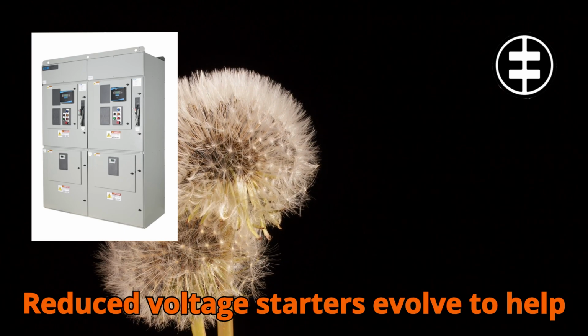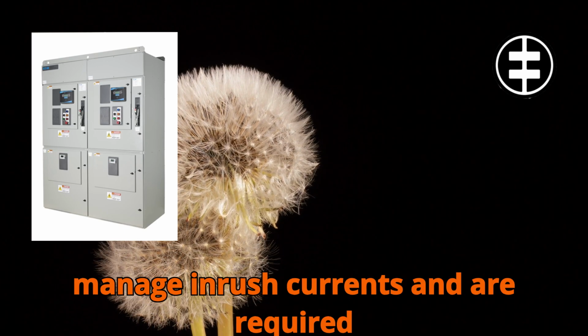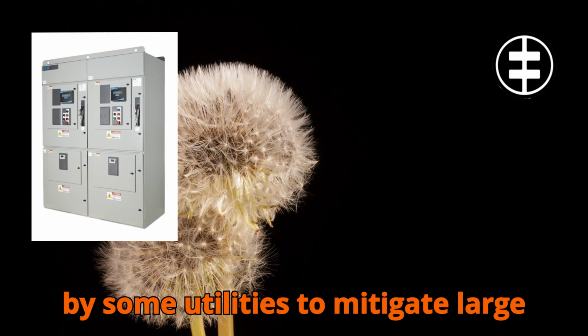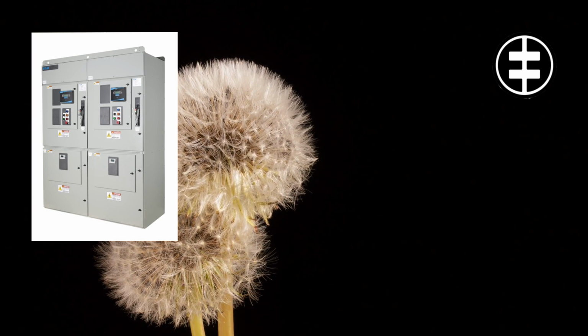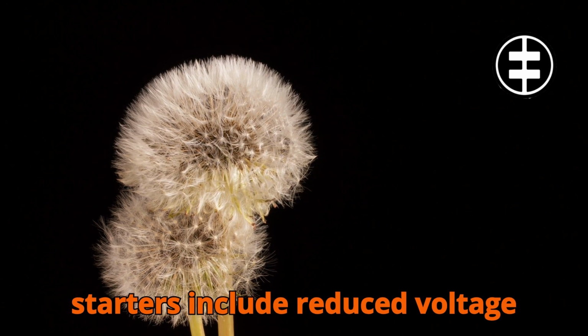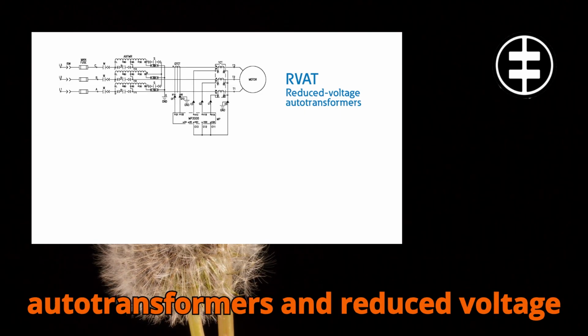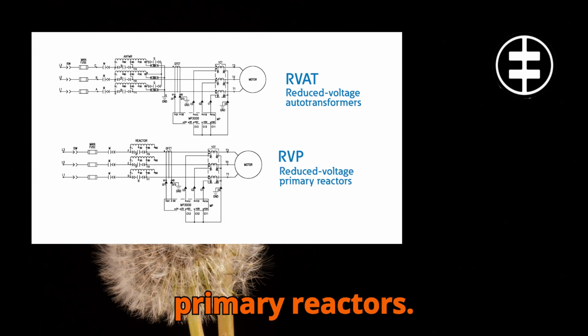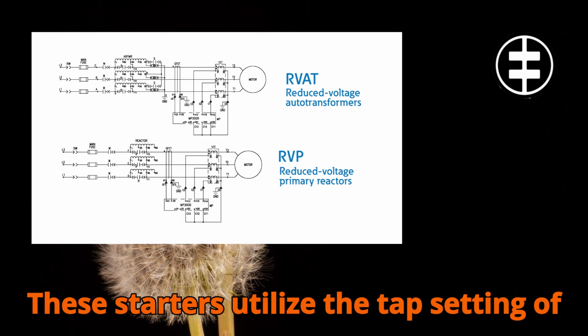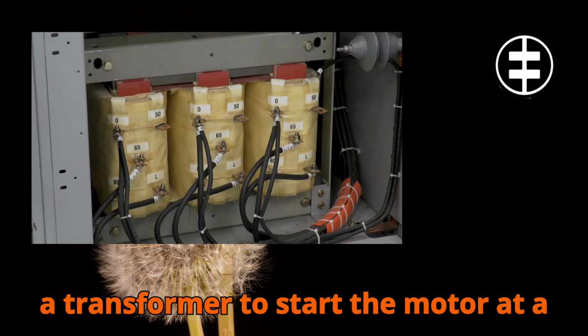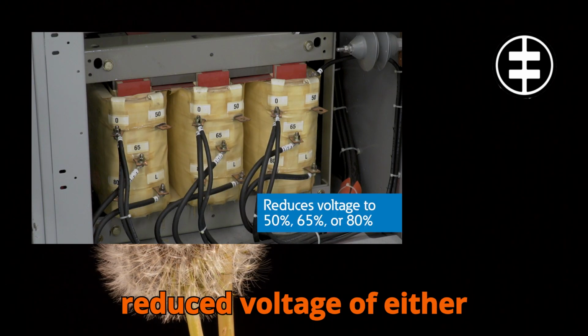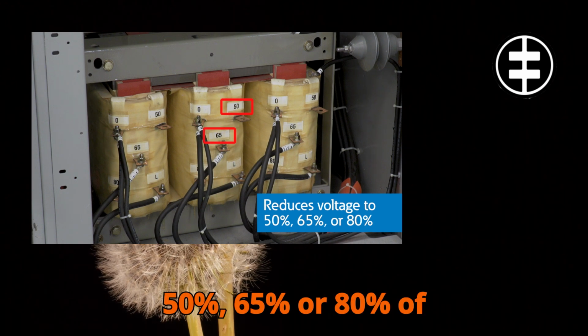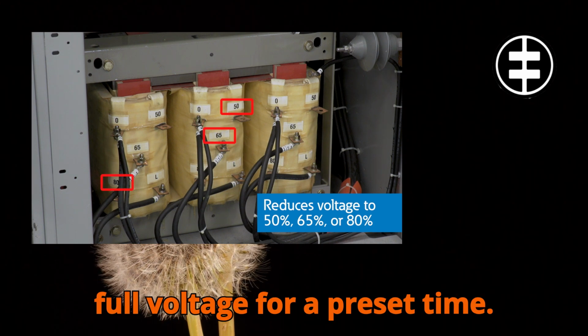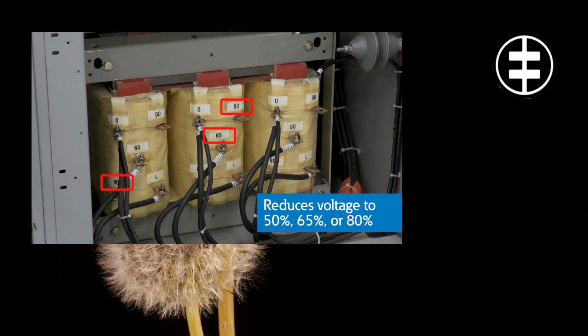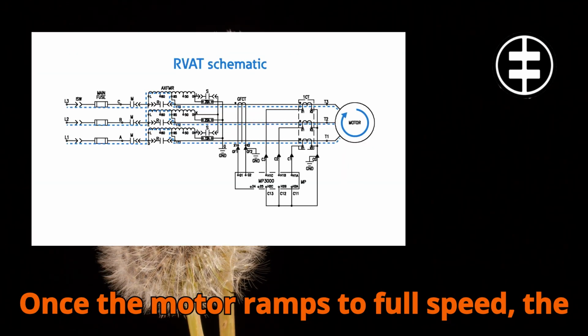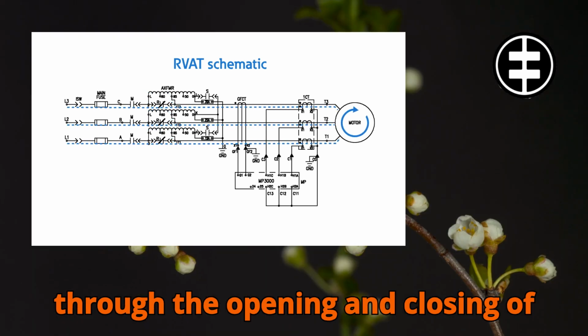Reduced voltage starters evolved to help manage inrush currents and are required by some utilities to mitigate large voltage drops during startup. The early forms of reduced voltage starters include reduced voltage autotransformers and reduced voltage primary reactors. These starters utilize the tap setting of a transformer to start the motor at a reduced voltage of either 50%, 65%, or 80% of full voltage for a preset time.